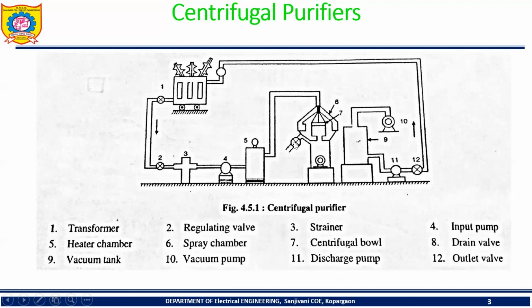Are you getting? Whatever heavy particles and heavy-weighted impurities are present can be extracted in a separate bowl over here. As we know, this bowl is rotated by means of a motor with very high speed. Whatever light-weighted oil is there can be drained out at the bottom. So at the bottom, we are getting the purified oil. That oil is shifted over here to a vacuum chamber. The vacuum chamber removes the moisture present in the transformer oil. Total moisture can be removed in the vacuum chamber, and the vacuum is maintained by means of this pump, called the vacuum pump.